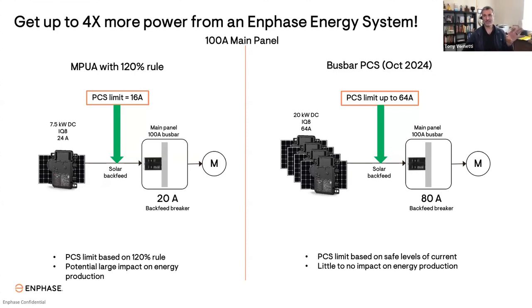With Busbar PCS, which is on the right here, the backfeed current can be as high as 64 amps. So the power output of the power backfeed from the solar back to the main panel can be 4 times higher with Busbar PCS.